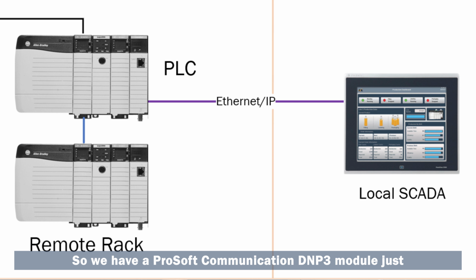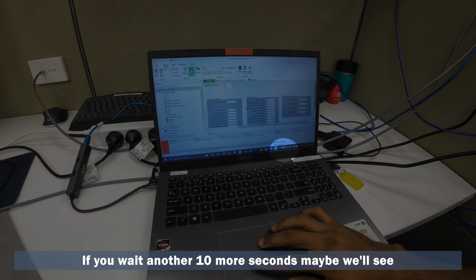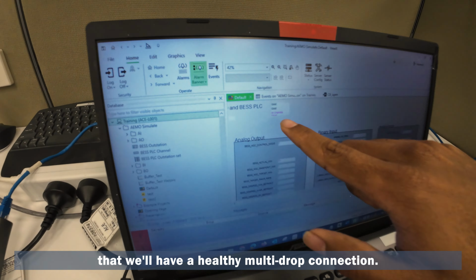We've ensured a successful trial with the hot standby switchover. If we disconnect this connection, for example, it simulates a real world scenario. Right now this server was the main; if we come over to our standby server, we see it's still standby, but it will take a while, approximately 30 seconds. Now we see this server has taken over as the main GeoSCADA server. If we wait another 10 seconds, we'll see a healthy multi-drop connection.